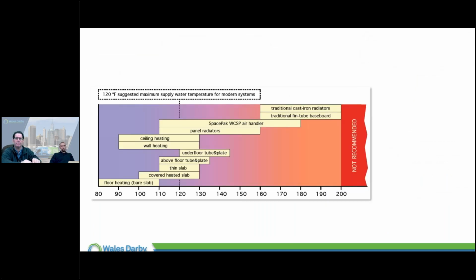Some cool stuff there. So here's one of my favorite slides. These are just some applications based off of water temp. We can see from the bottom all the way up to ceiling heat, those are all radiant-type applications: maybe underfloor, tube and plate, or what we call our quick track, joist track, moving the joist track and running these aluminum plates. Sometimes we need higher temps there, above 120, which might put us out there, but we've got to look at the application of BTUs.